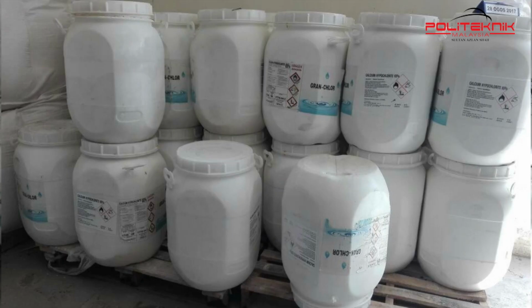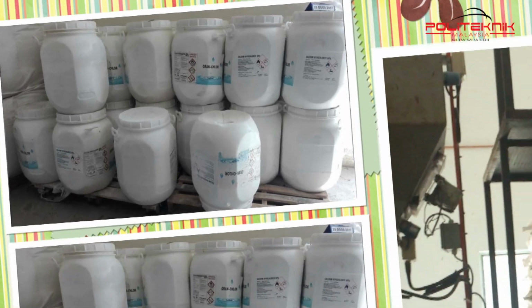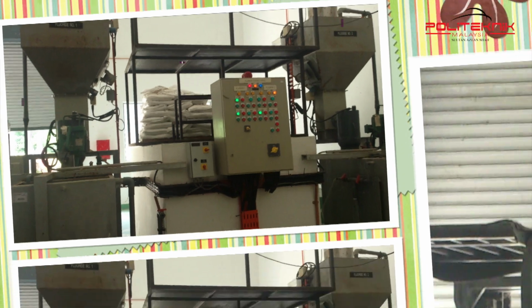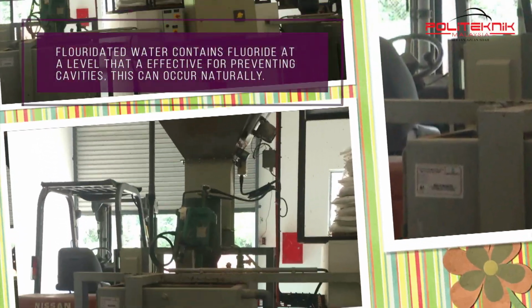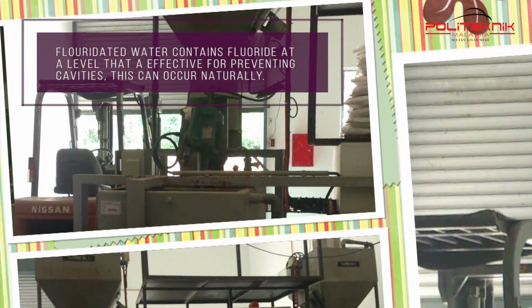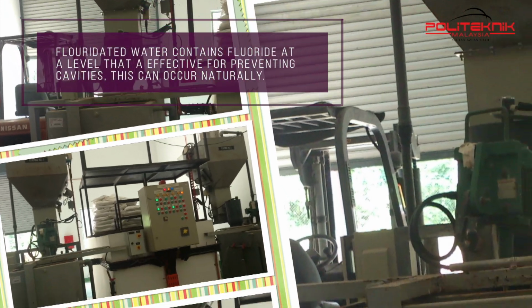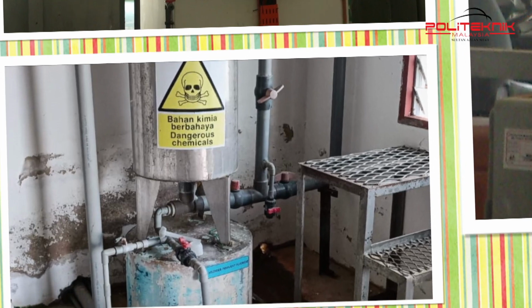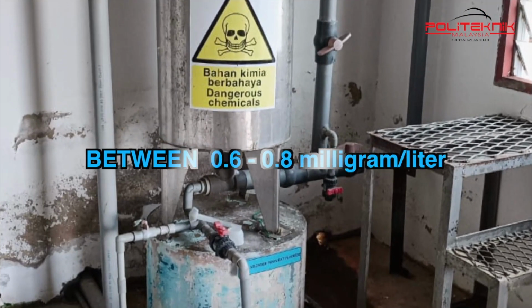Water fluoridation is the controlled adjustment of fluoride to a public water supply solely to reduce tooth decay. Fluoridated water contains fluoride at a level that is effective for preventing cavities. This can occur naturally or by adding fluoride. The dose allowed is between 0.6 to 0.8 mg per liter.